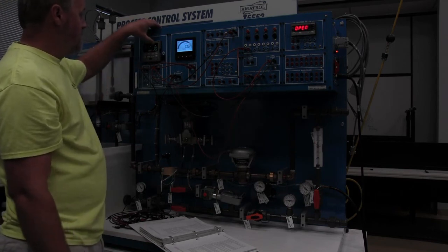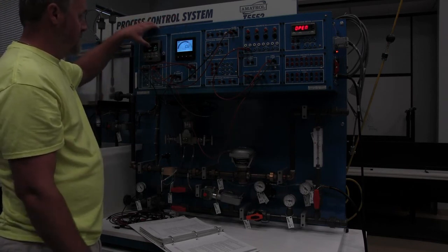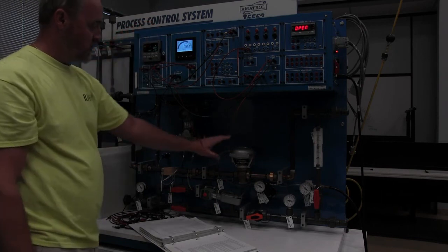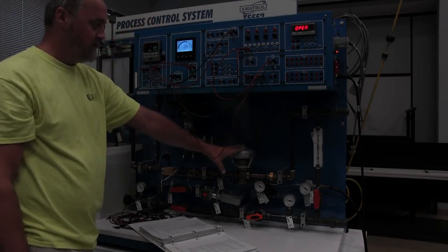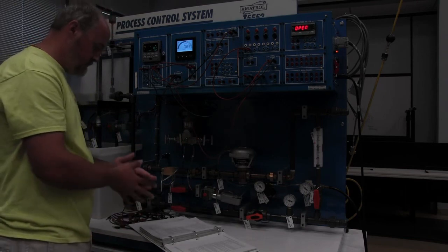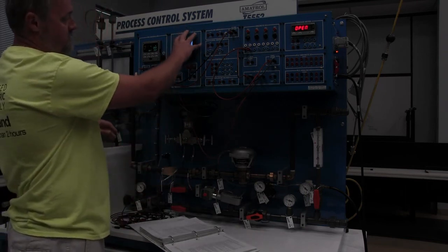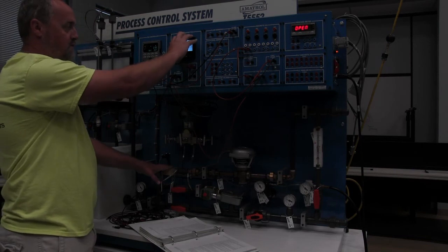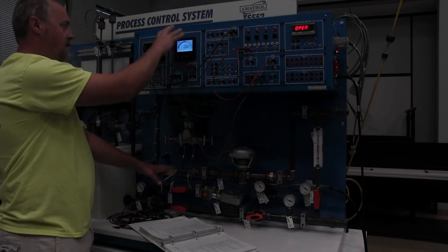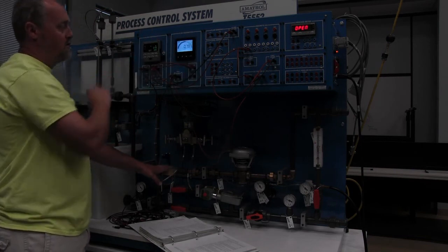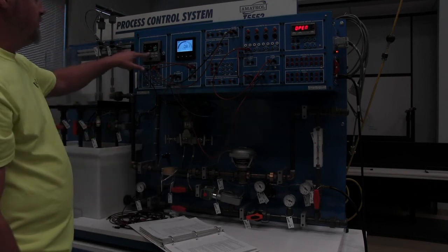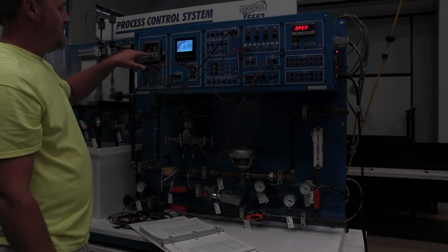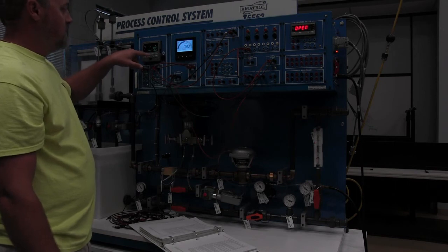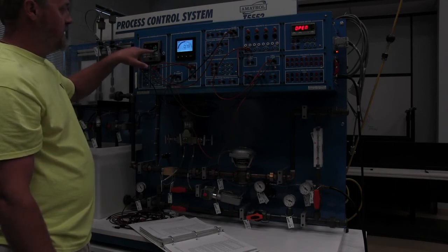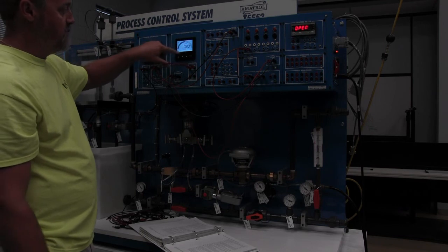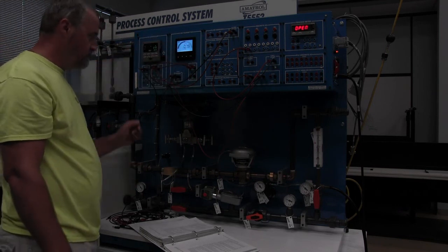Right now we're at 1 gallon per minute. We want to be at a 0.8, so the controller is outputting to close this flow control valve to slow the flow down. So this is reading the flow from the paddle wheel meter, and this is controlling the flow from the paddle wheel meter. So my set point is a 0.8. My output is fluctuating up and down to try to maintain that 0.8 gallons per minute flow.